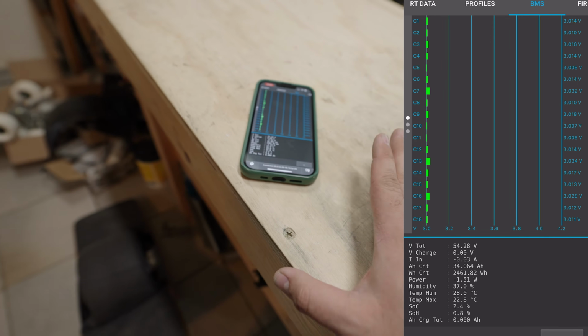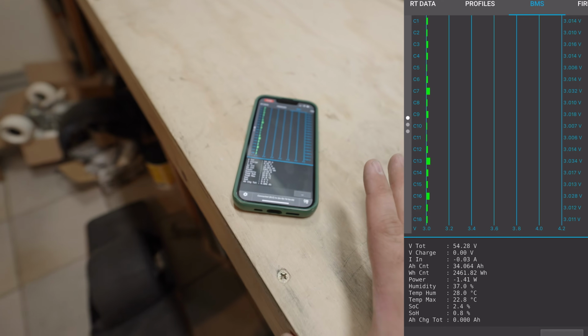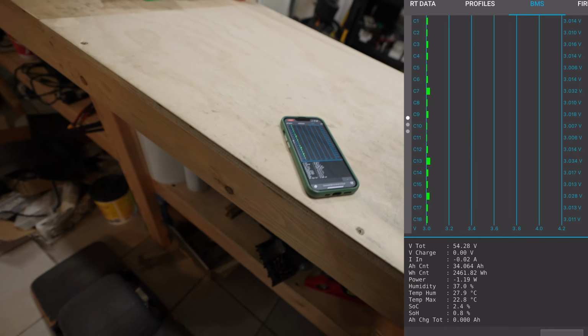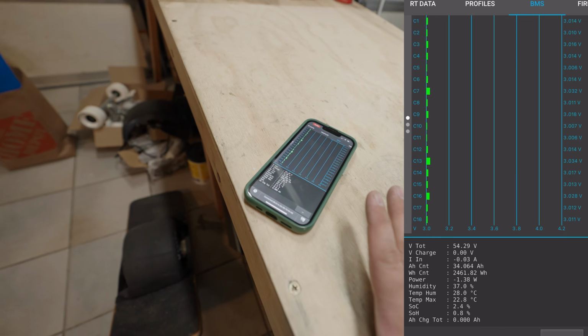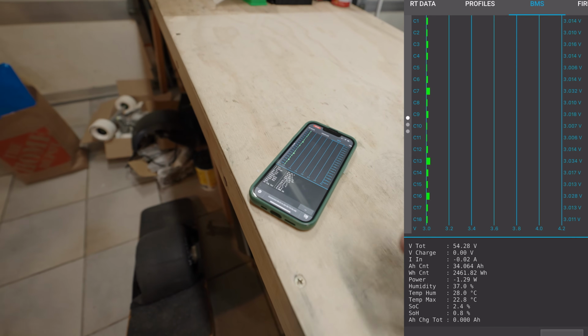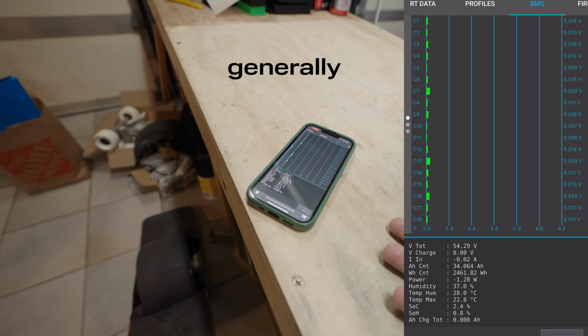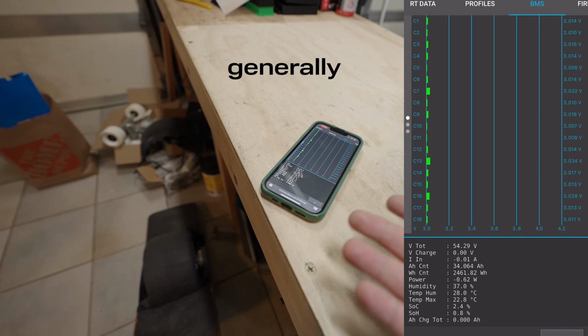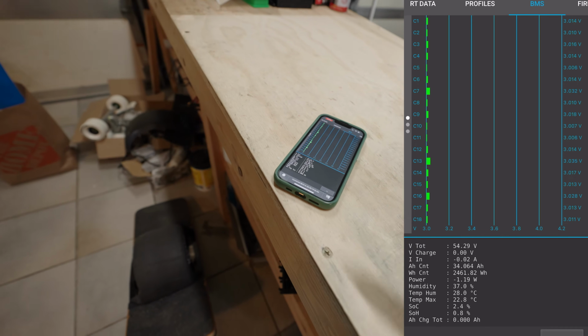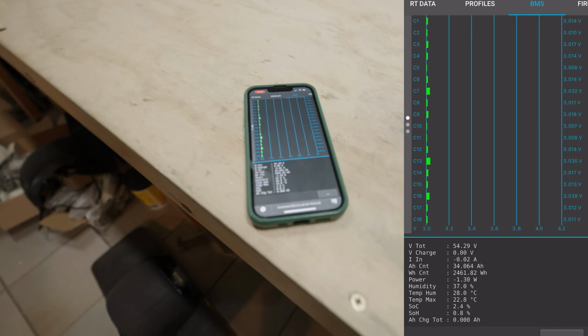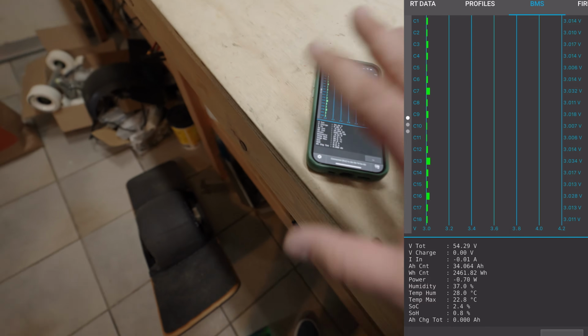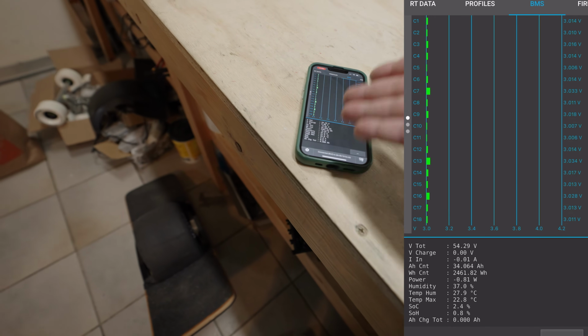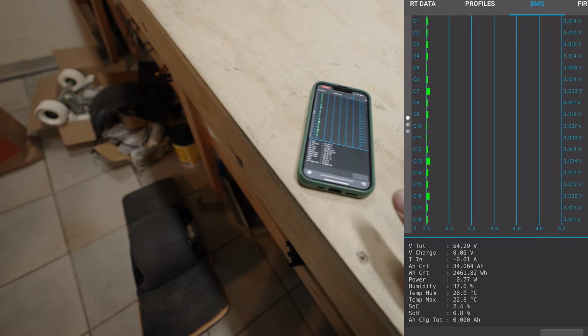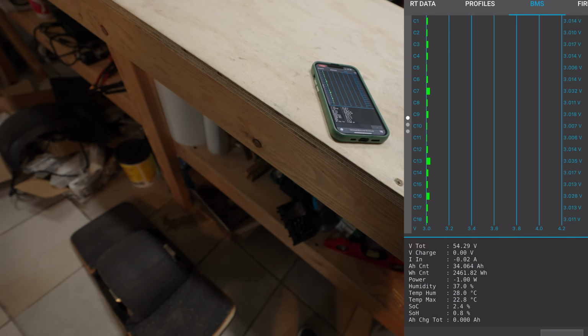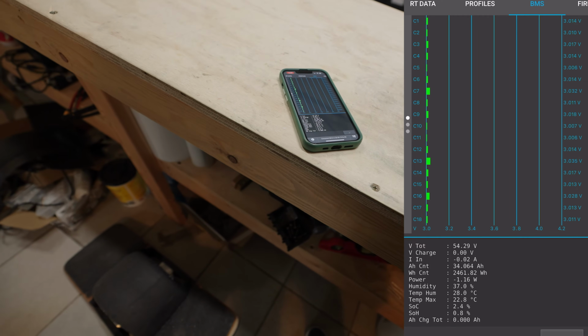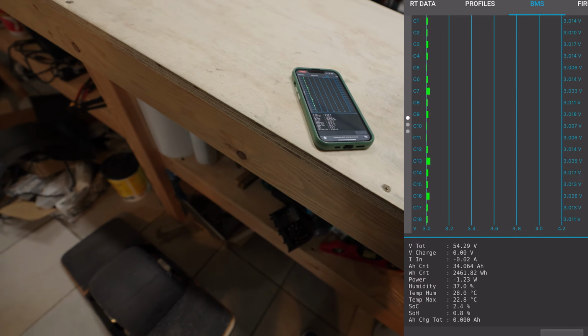Now it is safe and within manufacturer spec to take your battery down to 2.5 volts per cell. Most people don't, and you'll probably end up with a longer cycle life if you just discharge down to 3 volts. That said, you'll notice that at least as far as the data readout shows, the balance is not super great at the bottom, even though near nominal it was dead on even.